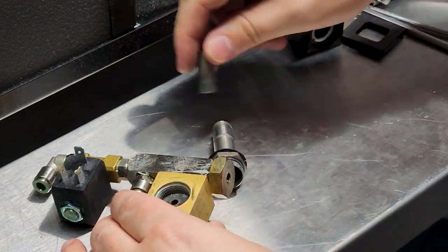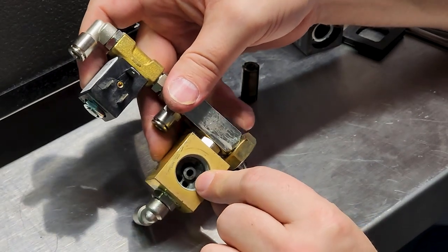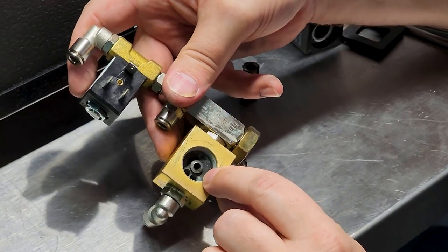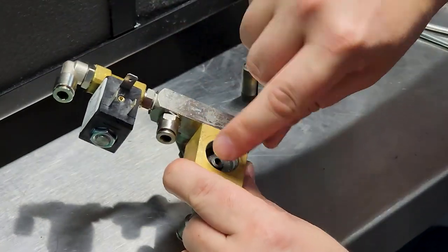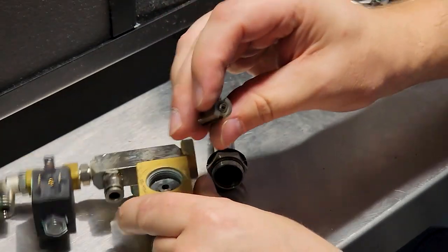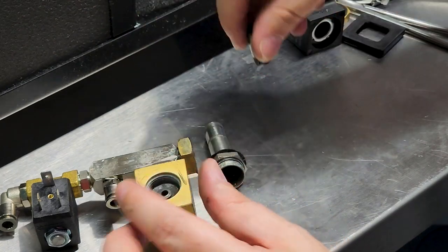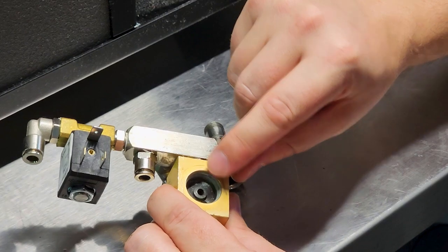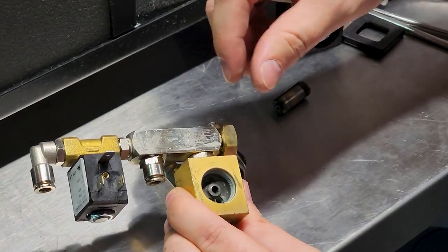In here is going to be your pilot, which is a tapered surface. This one is brass, and you can tell based on the wear pattern if you've got a leak or blow-by because it will be an uneven surface. I can take my finger on there and I can see that it's a nice even valve seat. I can see that also here - yep, nice even contact patch. So that's a good one. I might actually clean this up a little bit, but you want to take care if you're cleaning it up to make sure that you don't damage that pilot right there. Because if it gets uneven wear, this guy will be absolute garbage.